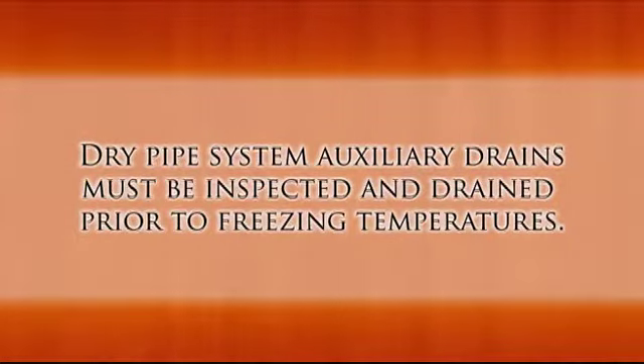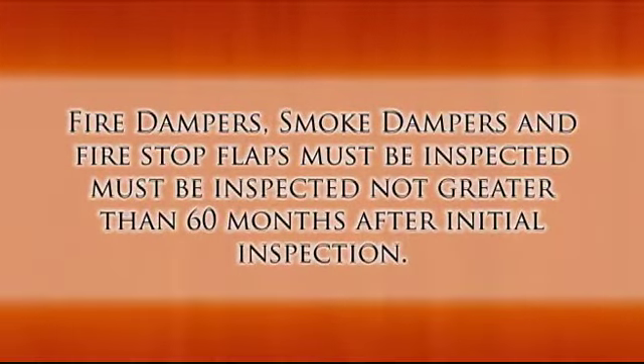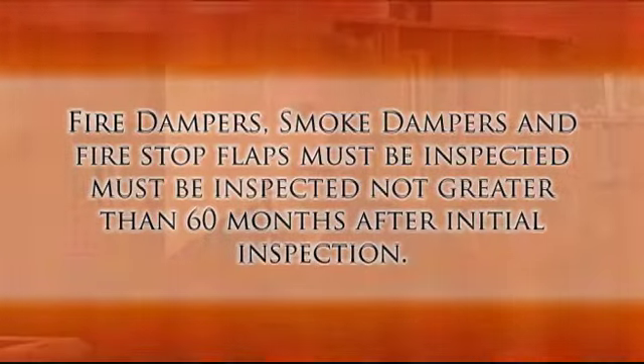Dry pipe sprinkler system auxiliary drains must be inspected and drained prior to freezing temperatures each winter to prevent the freezing of sprinkler pipes in those cold areas. Now, as well, fire dampers, smoke dampers, and fire stop flaps must be inspected at intervals not greater than 60 months after the initial inspection, which must be documented in your yearly section. Remember, it is your responsibility to ensure that all required tests and inspections are completed and entered in the maintenance log, and those that you are not required to complete yourself can all be coordinated through your school board.